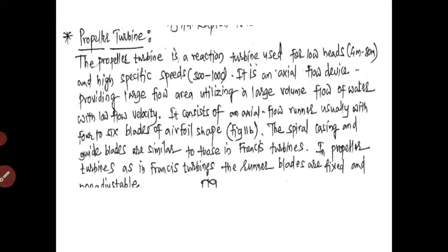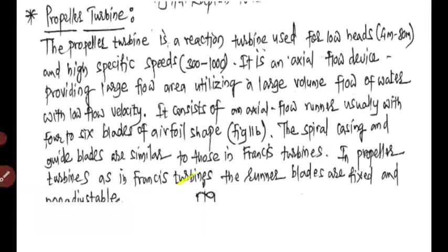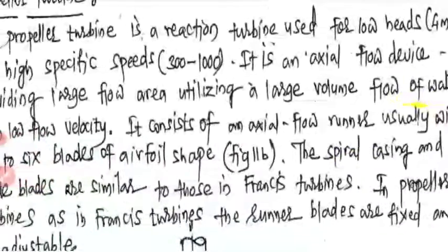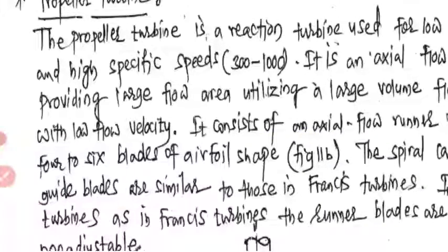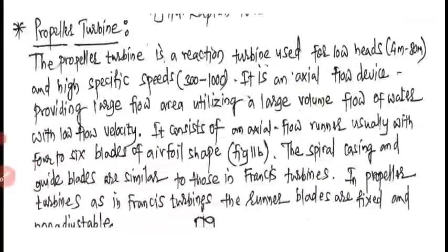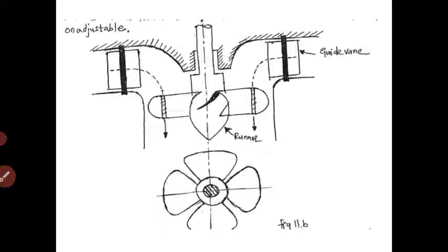The propeller turbine is a reaction turbine used for low heads of 4 to 80 meters and high specific speeds of 300 to 1000 rpm. It is an axial flow device providing a large flow area, utilizing a large volume flow of water with low flow velocity.